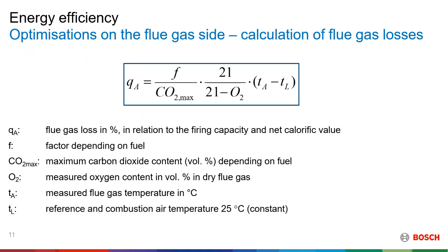So just the first section, losses in the flue gas. We have an equation which governs losses on the flue side, and looking at the parameters in the equation, the first one being the losses themselves. Then there's a factor depending on fuel, there's the CO2 max, which, considering our topic today of efficient steam generation, we cannot really remove or reduce the amount of CO2 unless you're reducing the amount of fuel you're burning, but CO2 will definitely be constant. Then the second parameter is oxygen, which is the amount of oxygen that you get in the flue gas. And then the last two parameters are the temperature of the flue gas, and comparing it with the air temperature of the surroundings.